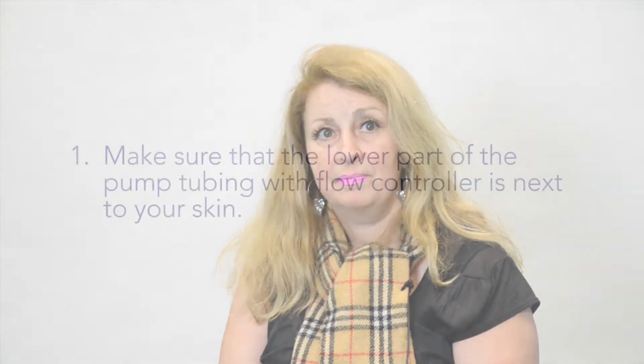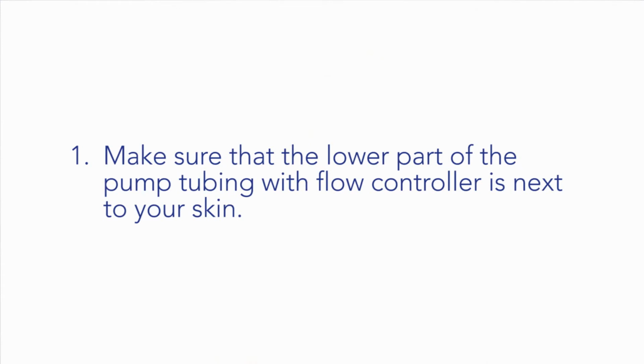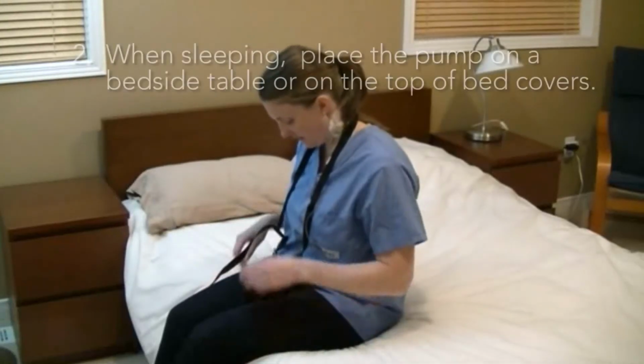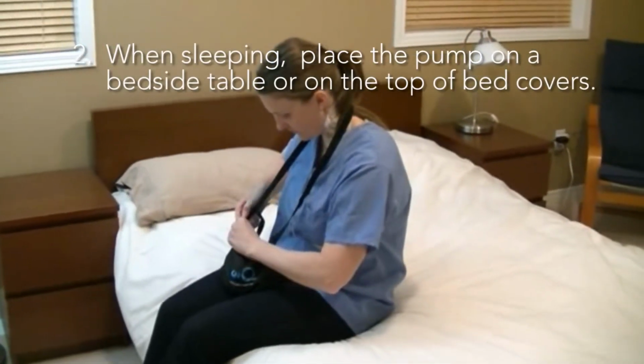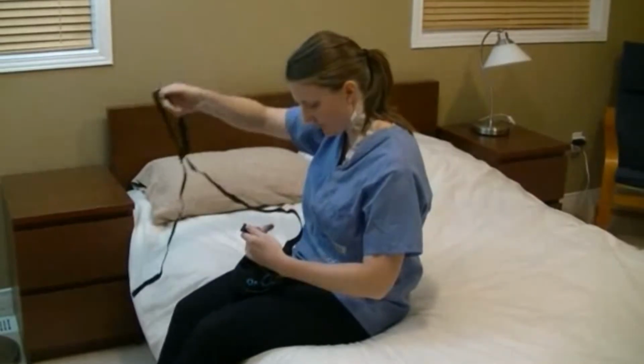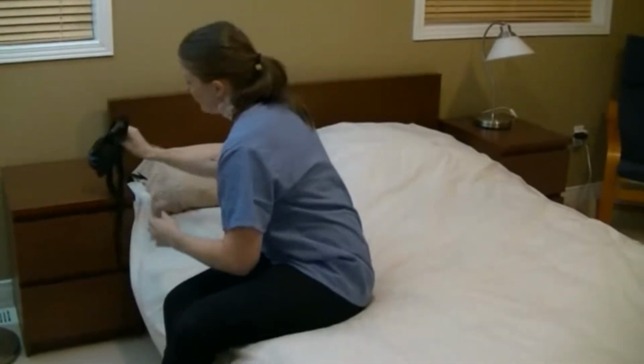The temperature will affect solution viscosity. Therefore, the flow rate on the pump will increase with an increase in temperature and decrease with a lower temperature. In order to prevent variability in the infusion rate, please follow these rules. Make sure that the lower part of the pump tubing with the flow controller is next to your skin. When your child or teen is sleeping, place the pump on a bedside table or on top of the bed covers. If you place the pump underneath the bed covers or a pillow, the pump may become too warm.